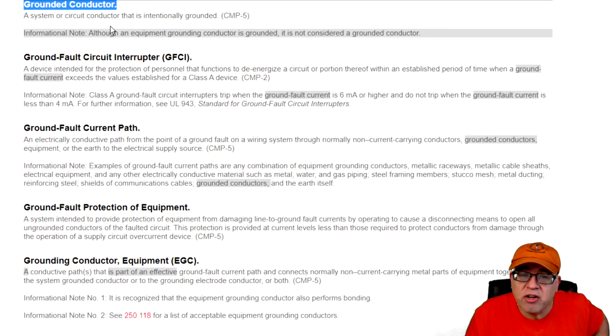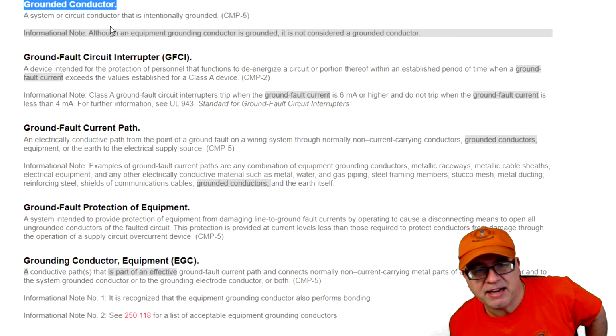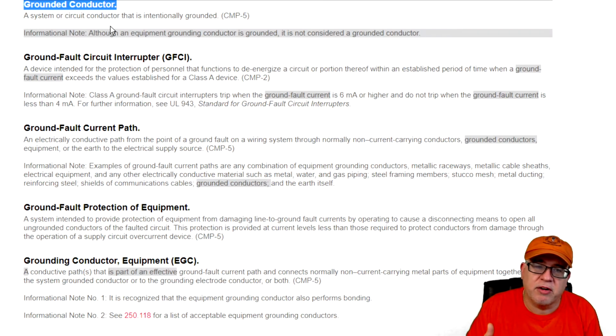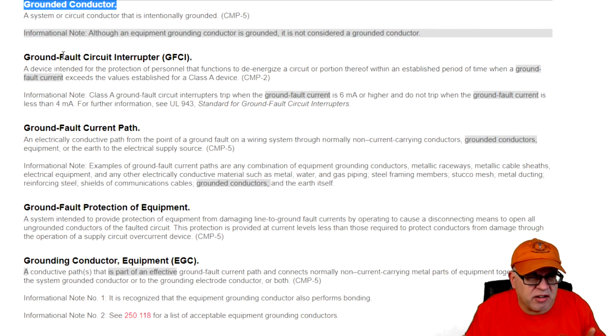You do have ungrounded systems, and that is where you don't have that connection. There it wouldn't be considered a grounded conductor. It's not grounded. You could have an ungrounded system. Not to confuse the term ungrounded conductor, because that has to do with all the hot conductors. They're all considered ungrounded conductors.